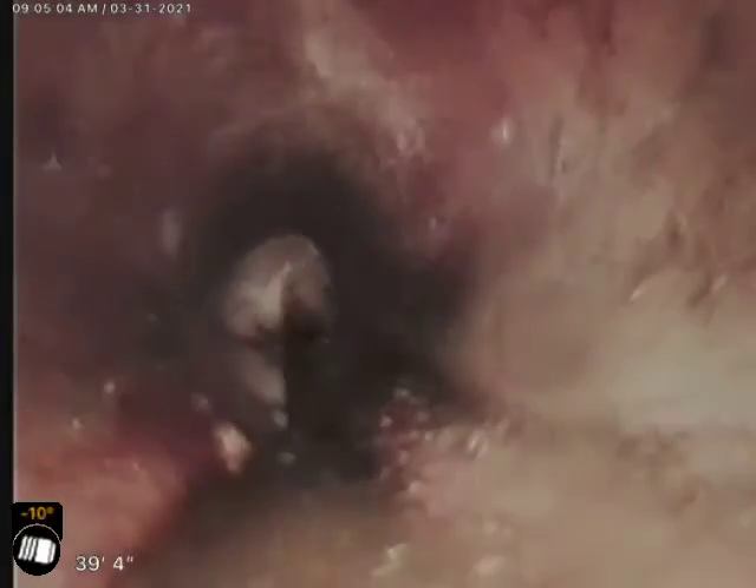Here we're going to go around a turn and pop in to a little sideline right here. Okay, here we come around. We've got a lot of sludge built up in this area. A lot of sludge and buildup down here off of this 2-inch PVC line in the mechanical room across from the water heater.